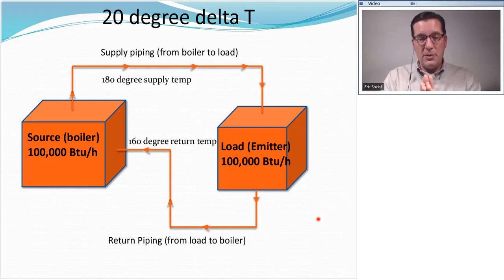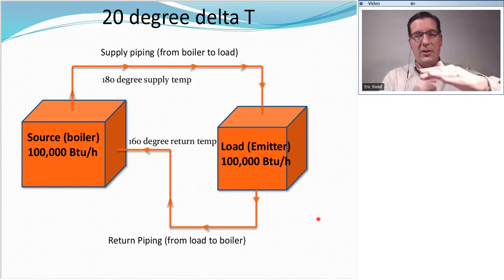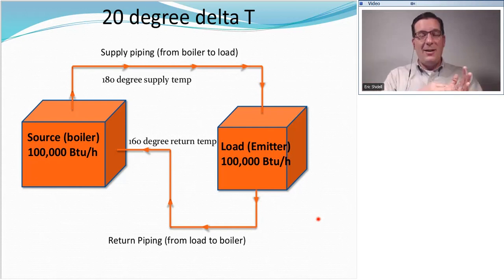And I'm just going to touch on this briefly now, and as we talk about circulators later, we'll talk about it a little more. The faster the water flows through a system, the less it changes in temperature. The less effective it is at picking up heat in the boiler, and the less effective it is at releasing heat in the emitter. If you've ever been playing with a lighter and you've been moving your hand across the lighter, you know that if you move your hand across the flame very quickly, it doesn't burn you. You don't really absorb any heat into your skin. But if you move your hand across the flame more slowly, well, now you burned yourself. And we all can imagine that. Well, imagine the same thing happening inside the boiler. Is that water is rushing through the boiler quickly, it's not very able to actually absorb any of the heat energy from that flame. Same thing on the load side.